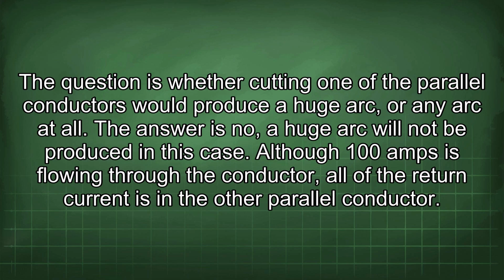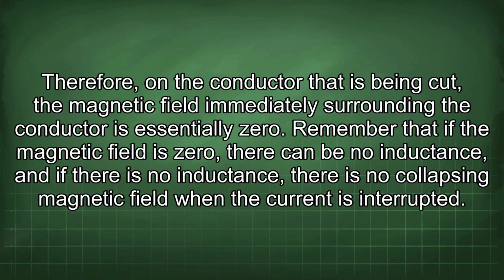Although 100 amps is flowing through the conductor, all of the return current is in the other parallel conductor. Therefore, on the conductor that is being cut, the magnetic field immediately surrounding the conductor is essentially zero. Remember that if the magnetic field is zero, there can be no inductance, and if there is no inductance, there is no collapsing magnetic field when the current is interrupted.